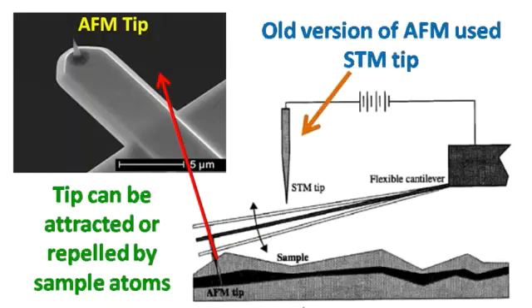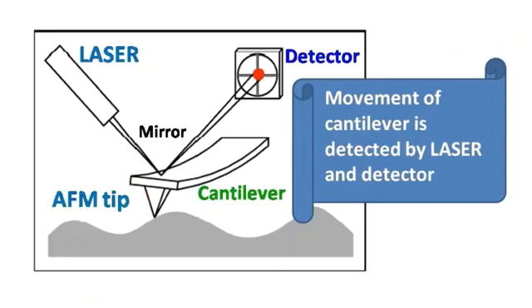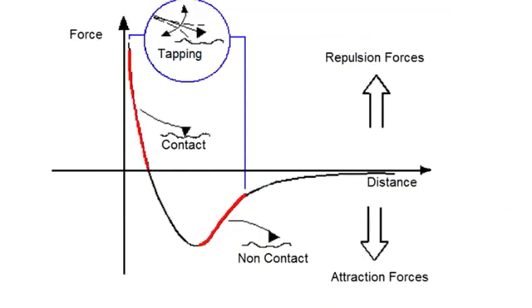The earlier versions of the atomic force microscope employed a scanning tunneling microscope tip, which recorded the oscillation of the cantilever based on the tunneling current obtained. However, it was later replaced by a laser and a mirror, which would record the oscillation of the tip. As the cantilever moves up and down depending on the sample surface, the laser is deflected and gives information about the sample surface. There are three main modes in which the atomic force microscope is operated: contact mode, non-contact mode, and tapping mode.